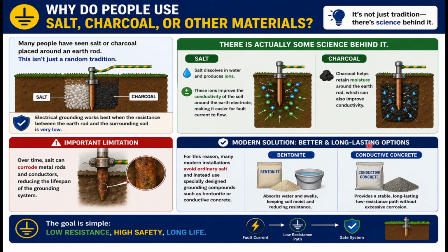So in so many cases and in so many instances, you are going to see that when electricians or technicians try to bury the earth rod, they put some materials on the ground like charcoal, salt. Some people even put lemons and all of that. These things are used to help increase the conductivity of the soil around the earth rod. That's why we put salt, because salt dissolves in water and produces ions. These ions improve the conductivity of the soil around the earth rod. That is one of the reasons. Charcoal helps to retain moisture around the earth rod, which can improve the conductivity.